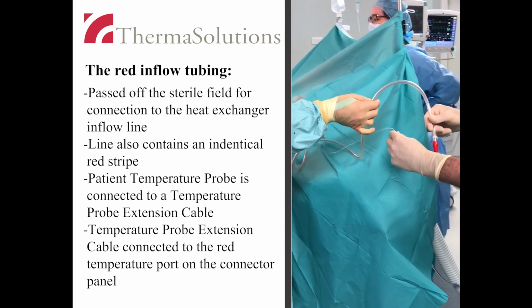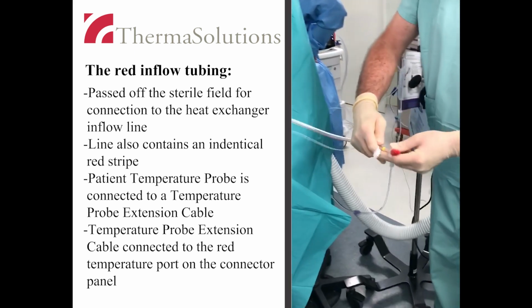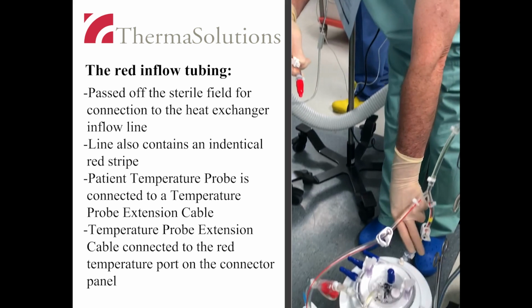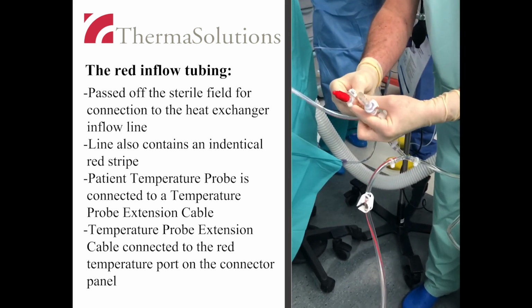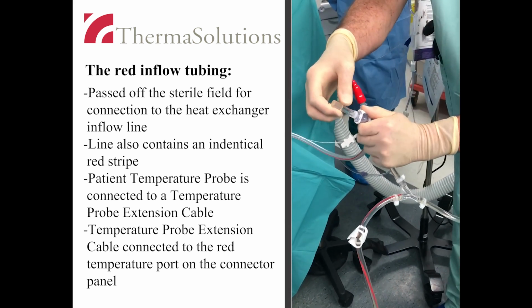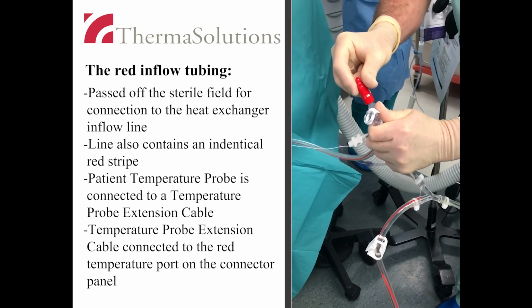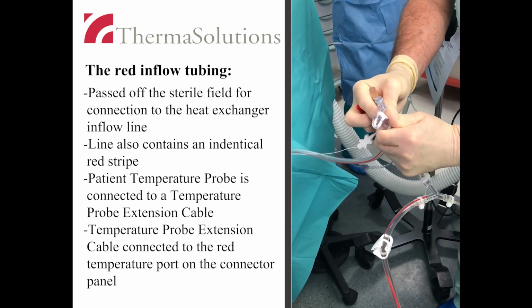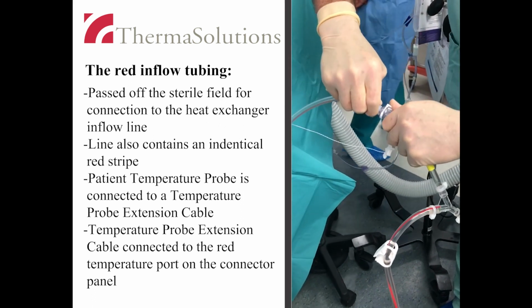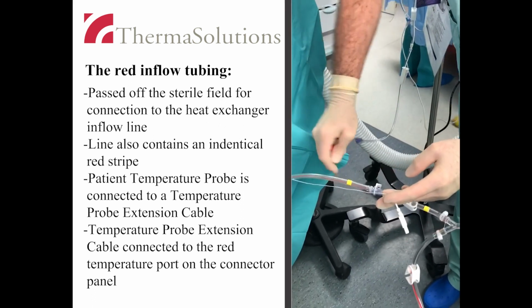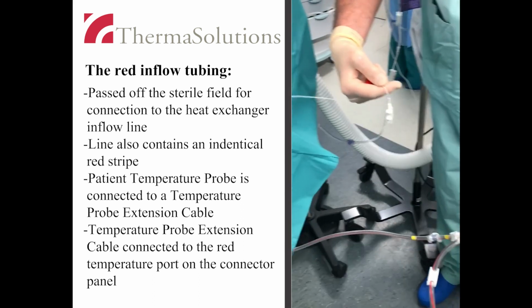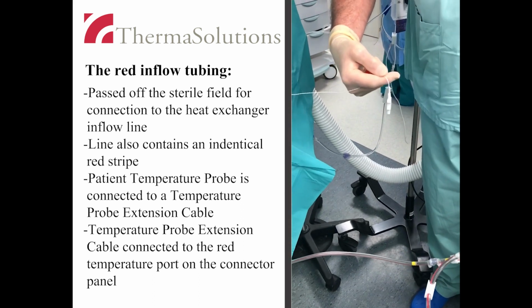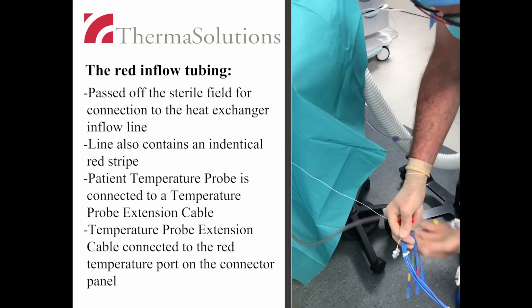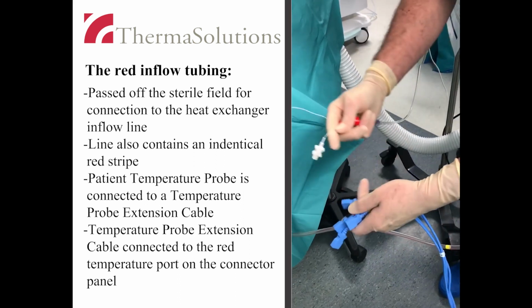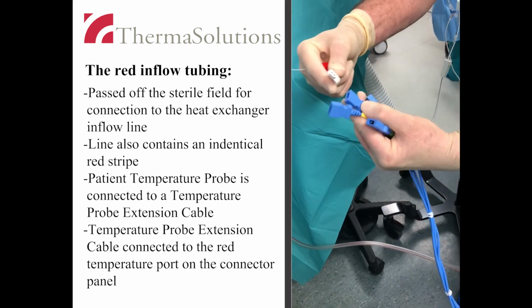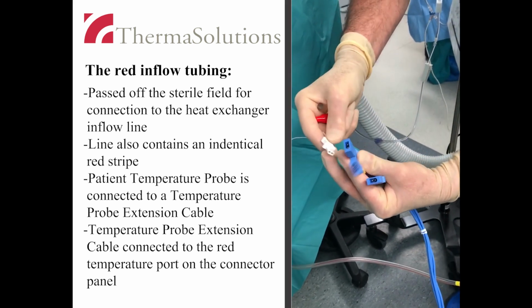The red inflow tubing is passed off the sterile field for connection to the heat exchanger inflow line. This line also contains an identical red stripe. The patient temperature probe is connected to a temperature probe extension cable. This temperature probe extension cable should be connected to the red temperature port on the connector panel.